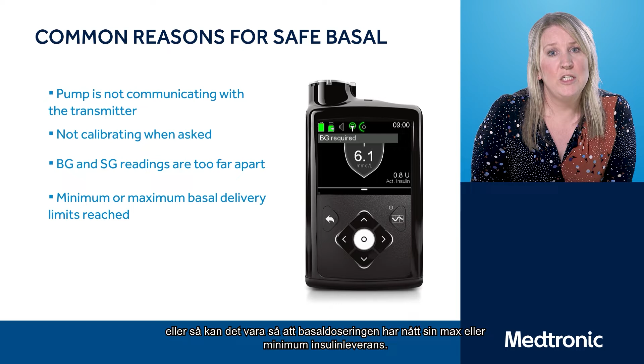So what do you need to do when you exit auto mode? Rest assured you will automatically go into manual mode. But as our aim is to keep you the maximum time in auto mode, we may need to take some action. And it's worth having a look at your auto mode readiness screen to see what action needs to be taken. So for example, on the screen you will see an example of this status screen. If there is a question mark in the shield next to blood glucose required, then you simply need to link in a blood glucose reading, and that will help auto mode get back into its position again.